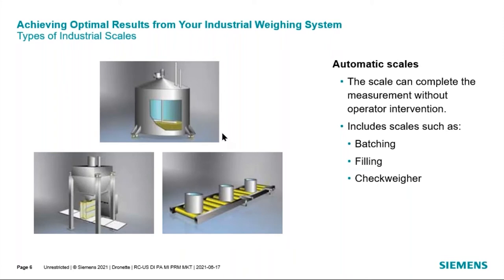Automatic scales have the controls built into the weighing electronics to complete the weight measurement. Examples include batching systems, filling systems, and checkweighers. With a batching system, you can have two types: a loss-in-weight batching system or a gain-in-weight batching system. With a loss-in-weight system, you have your raw material bins on load cells, and the scale monitors how much material is being transferred from the raw material bin into the mixing bin, stopping the transfer when the appropriate amount is added.